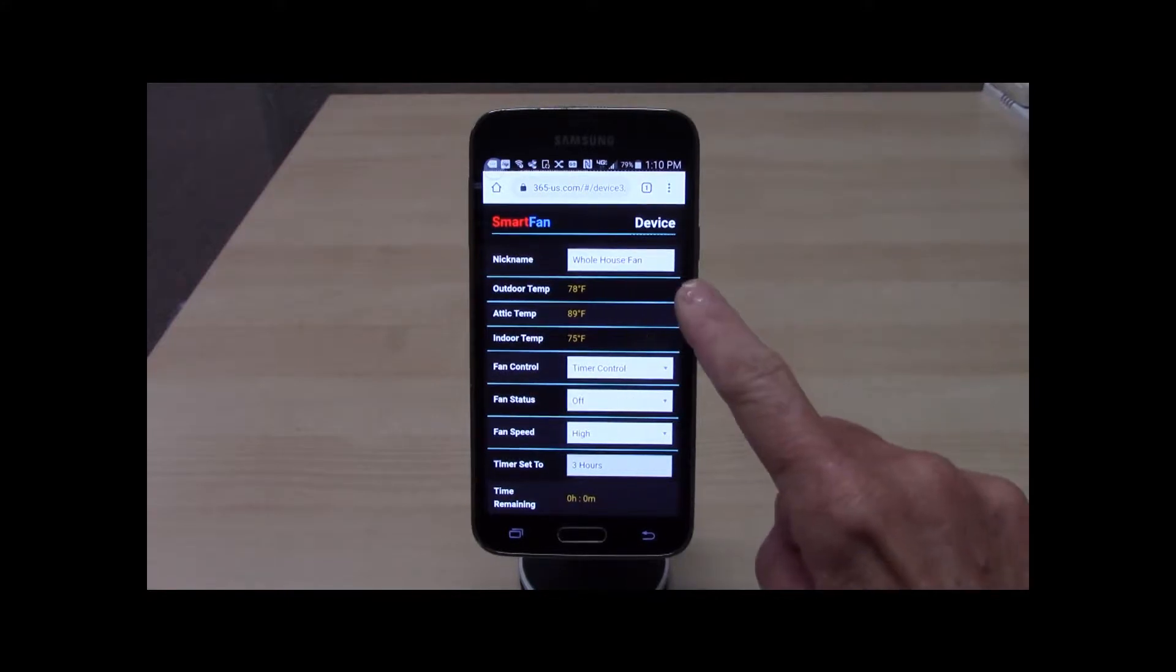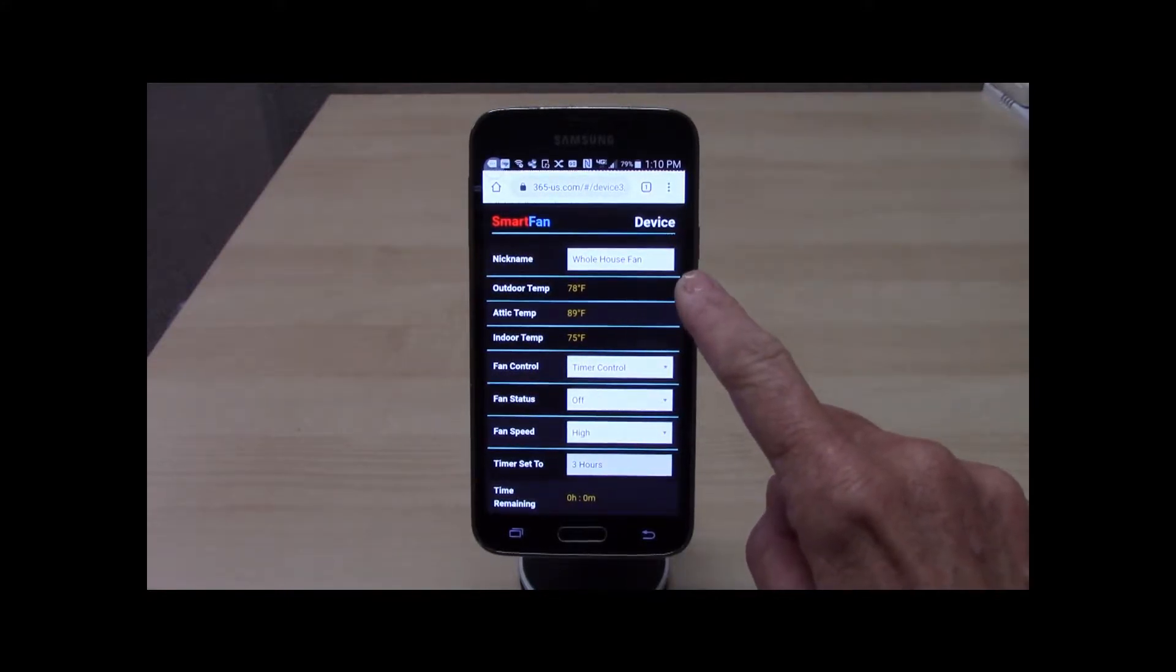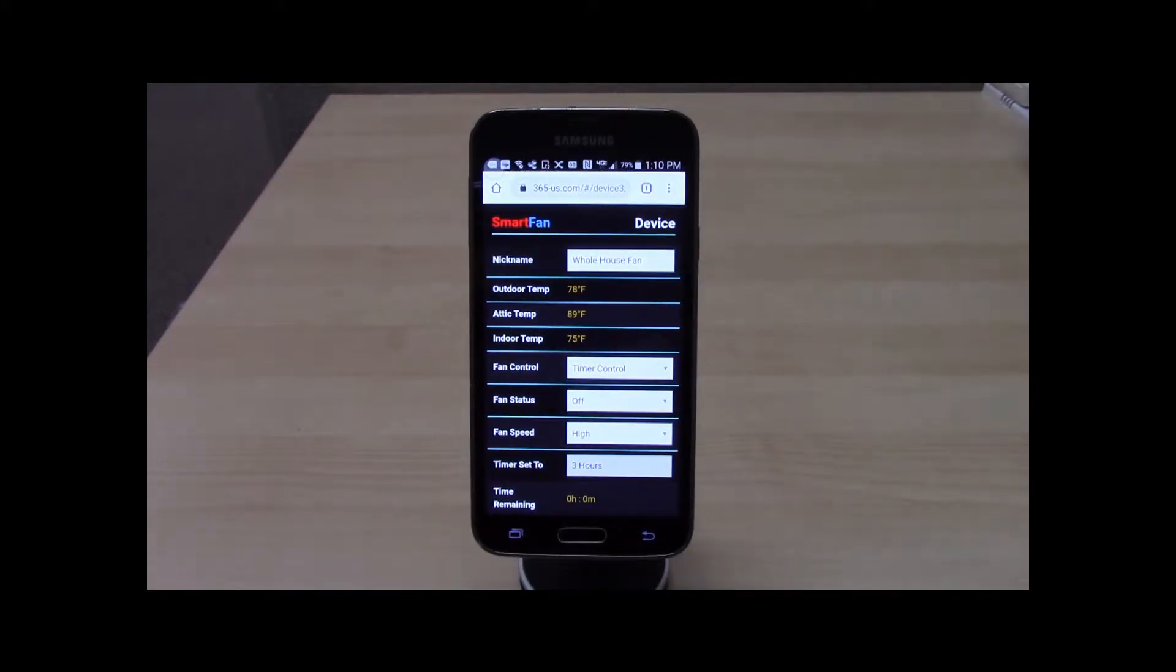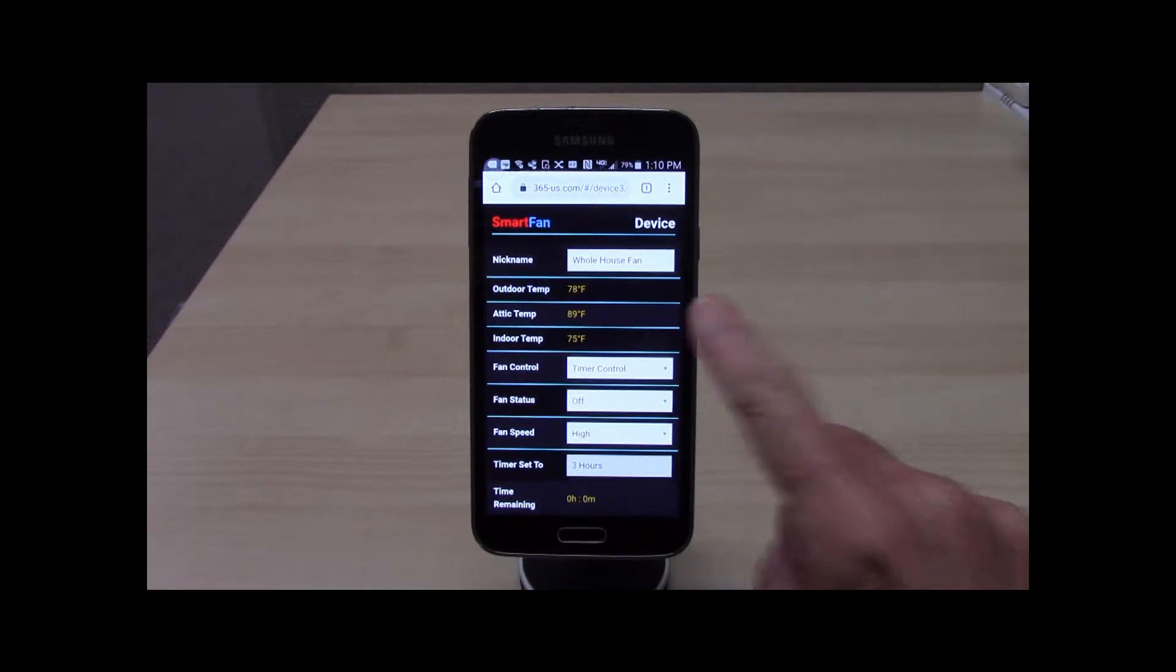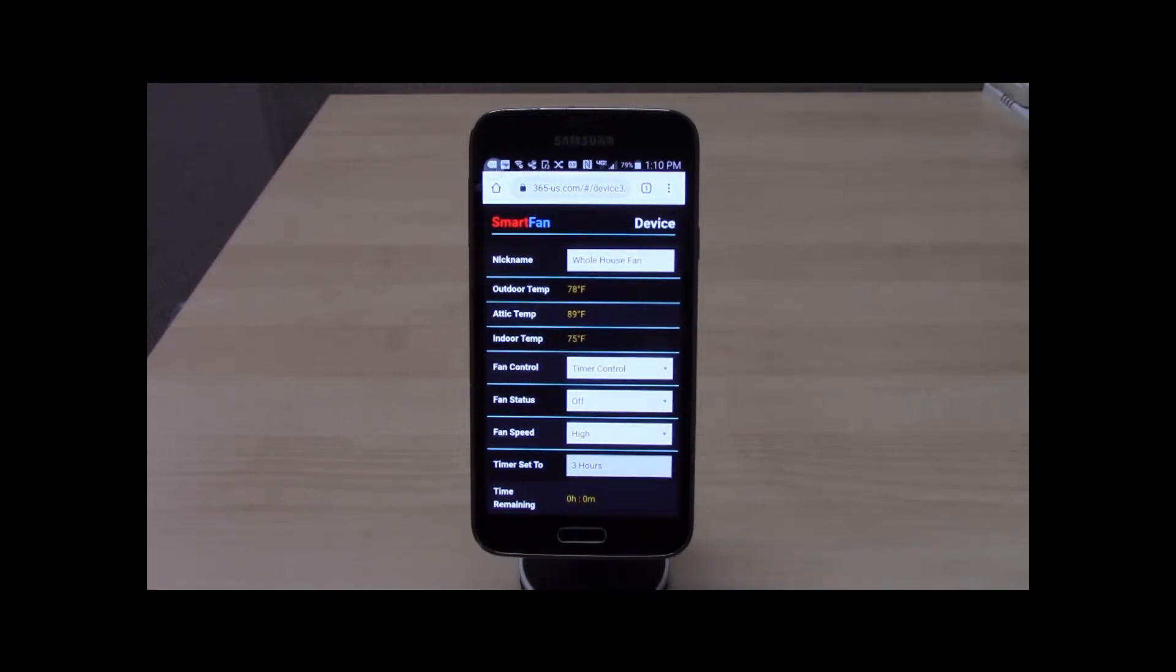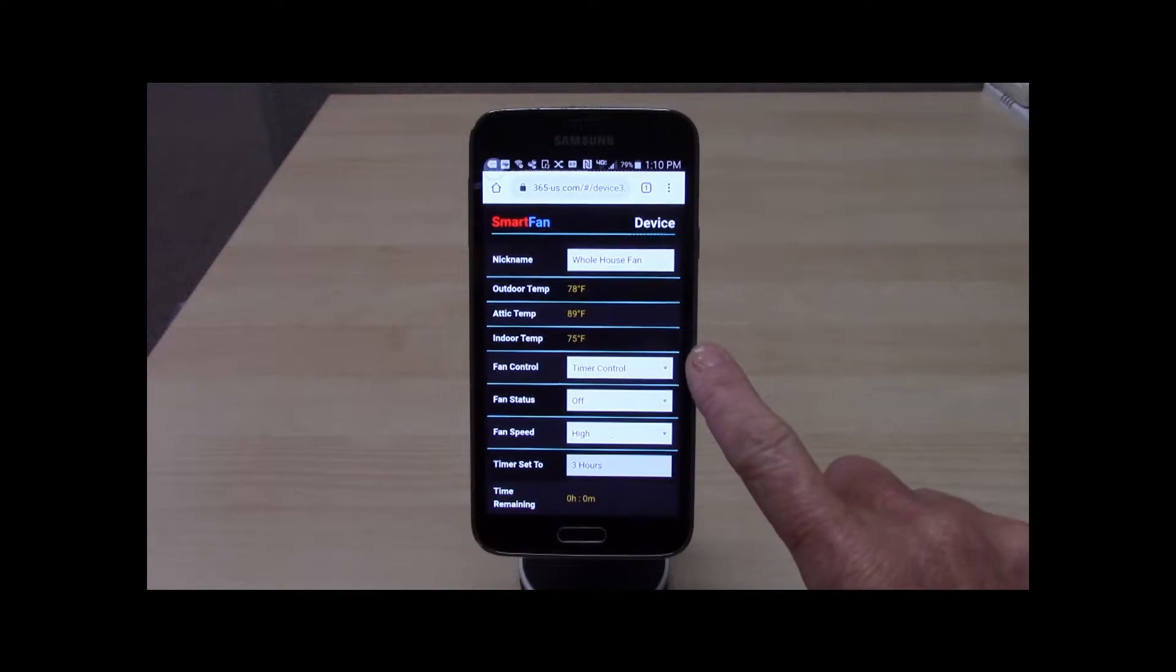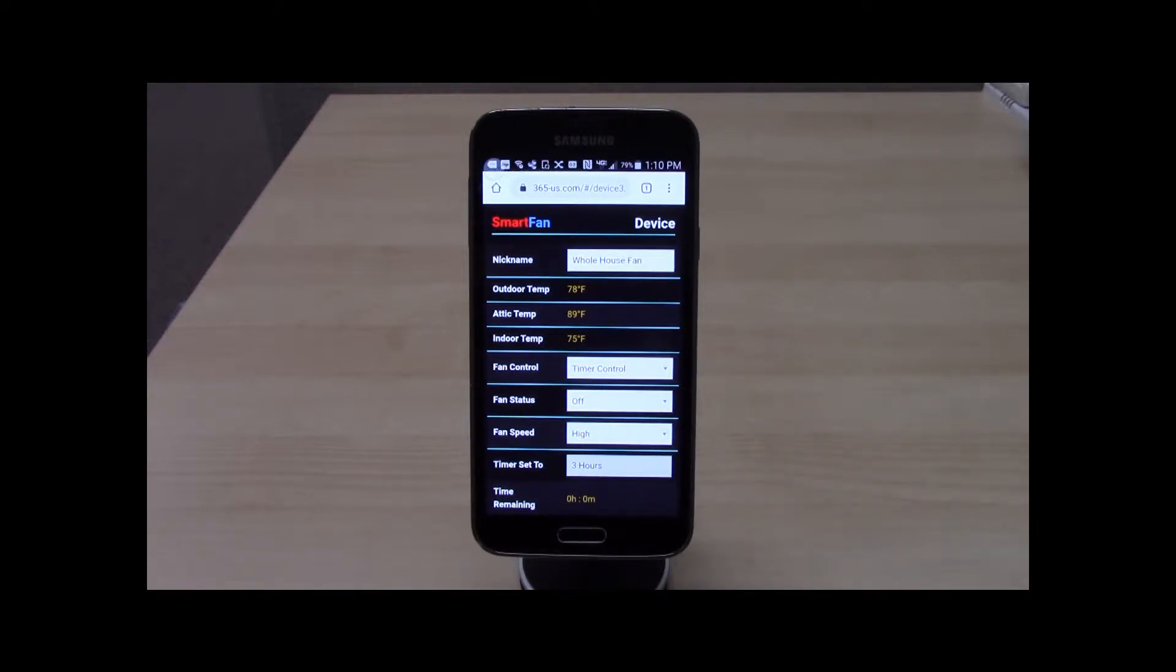Nickname enables the homeowner to give their device a meaningful name. The outdoor temperature is used to delay fan operation if the outdoor temperature is too warm to provide cooling and is only displayed if an outdoor temperature sensor has been installed. The indoor temperature is displayed and is used for temperature control, which is selected in Fan Control.